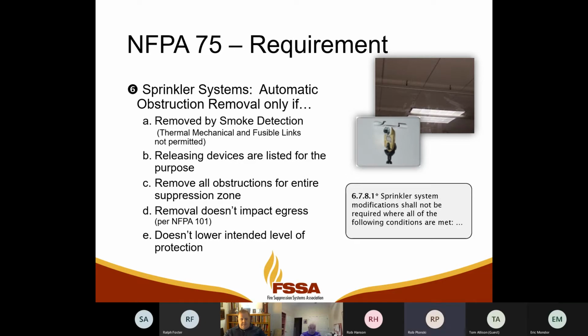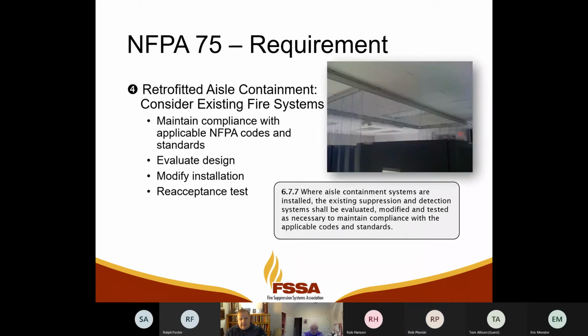Hey, Lee? Yeah. Real quick, is any of this retroactive? That was a question that just came in. Absolutely retroactive. I mean, that's this one right back here. Number 4, and in the code that's 6.7.7, where aisle containment systems are installed, the existing suppression and detection systems shall be evaluated, modified, and tested as necessary to maintain compliance with the applicable codes and standards. To me, that means retroactive. Okay, thank you. Yeah.